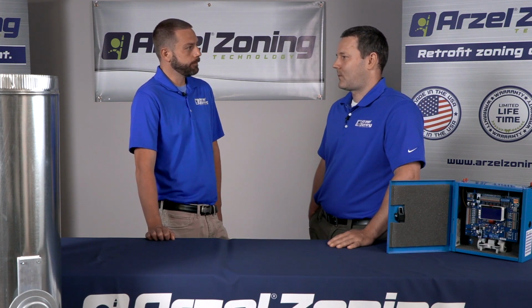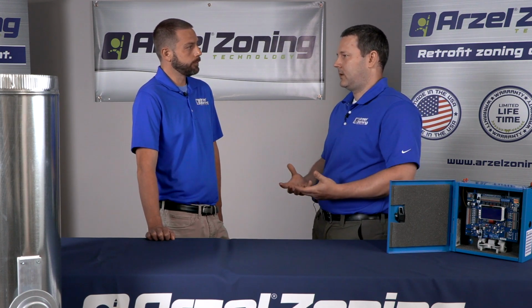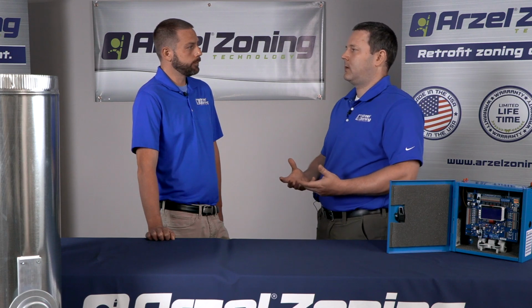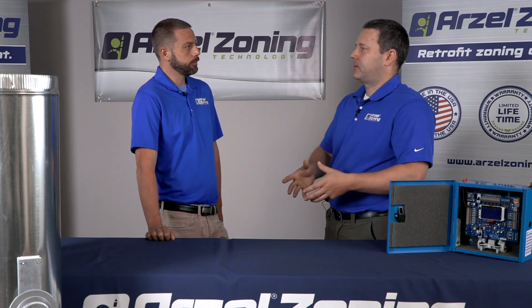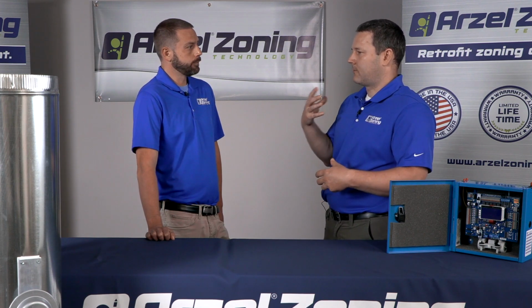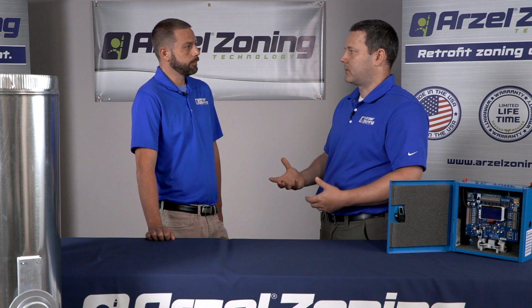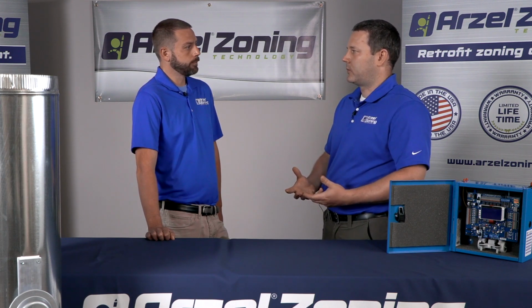I've heard that zoning can reduce the life expectancy of your HVAC equipment. Is this true? That's really a common misconception. The reduction of life on the equipment comes right down to actual design. If my furnace is already too small or too large for my ductwork, so I'm running high static before I even put zoning in, then I'm going to run into a problem with life expectancy on that equipment.